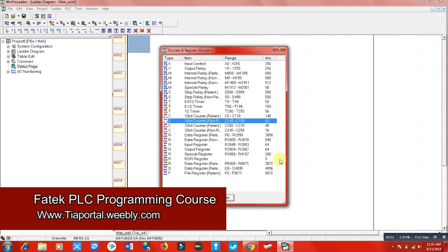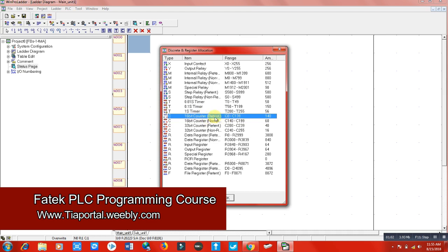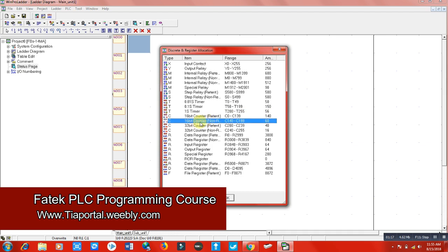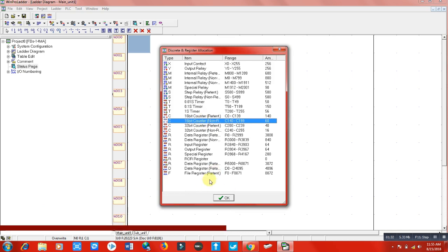Here we have 16-bit retentive counters starting from C0 to C139, so we can use 140 counters. We also have 16-bit non-retentive counters from C140 to C199, which means we have 60 non-retentive counters we can use. Let's use these types of counters. We will start from C0, which is retentive counters.